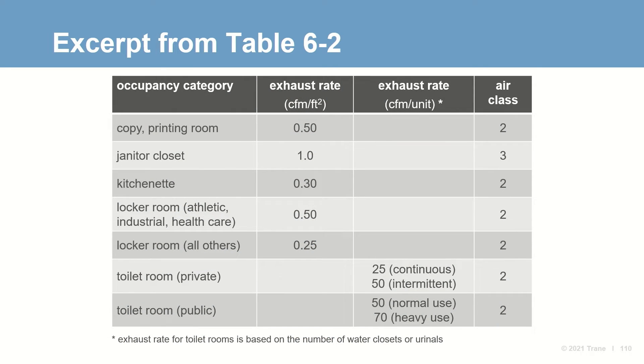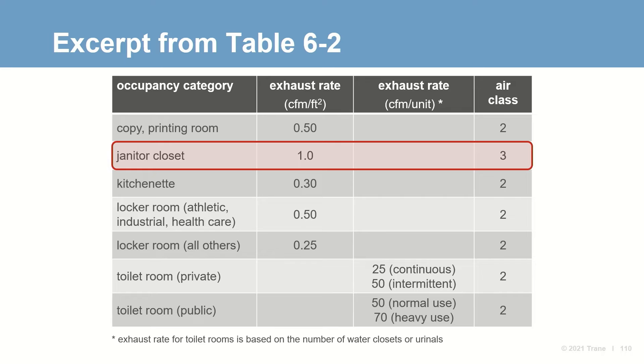When using the prescriptive path, here's an excerpt from the table listing minimum exhaust rates for those specific occupancy categories where contaminants are likely to be generated. For example, a janitor's closet must be designed to exhaust 1 CFM per square foot of floor area when in use.